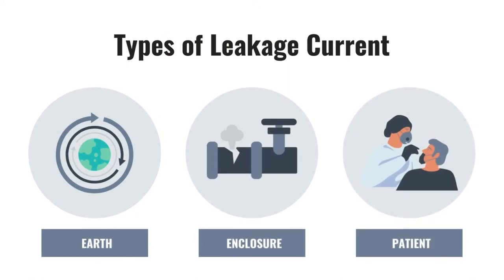Several types of leakage currents have been defined: earth, enclosure, and patient. Patient leakage current flows from the applied part of the medical device through a patient to ground, and can result in waste of energy and be dangerous to human life.